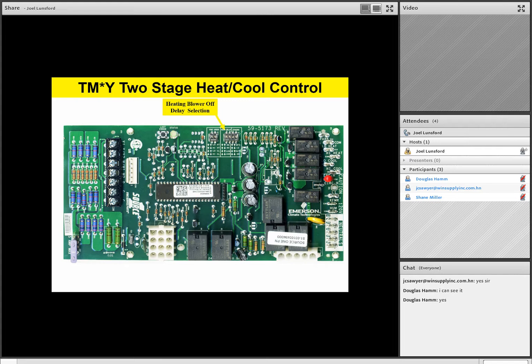Now the next thing we're going to talk about is staging. This is something unique to the TM9Y and the TM9V, the variable speed and the two-stage control board we're talking about. We mentioned earlier that if you're stuck with a single-stage thermostat, you're going to land your low-voltage wires from your thermostat on the W/W1 terminal. Well, you can actually get some staging function with these dip switches. So instead of just running on single stage all the time, this staging function will allow single stage thermostat operation on this high efficiency ECM motor control board.